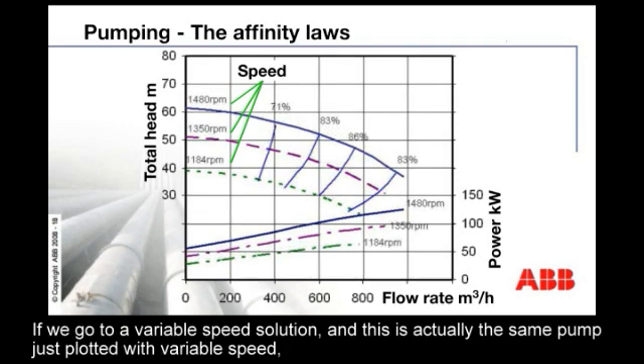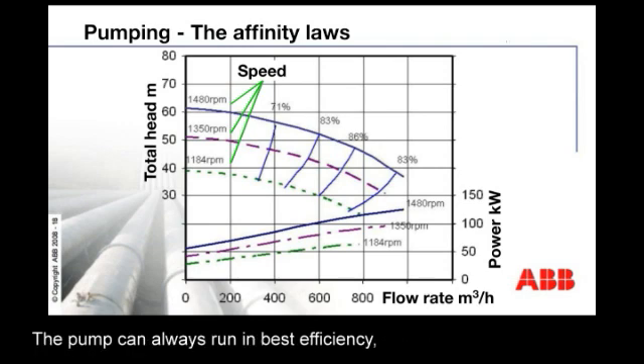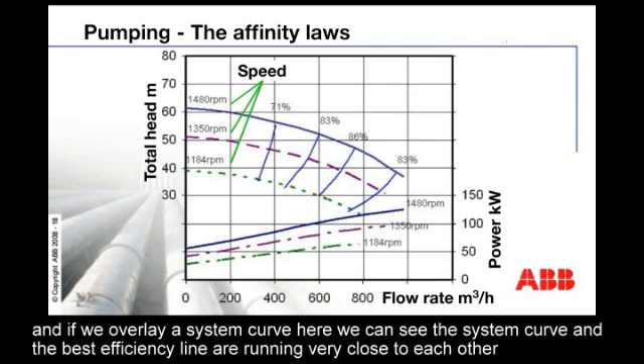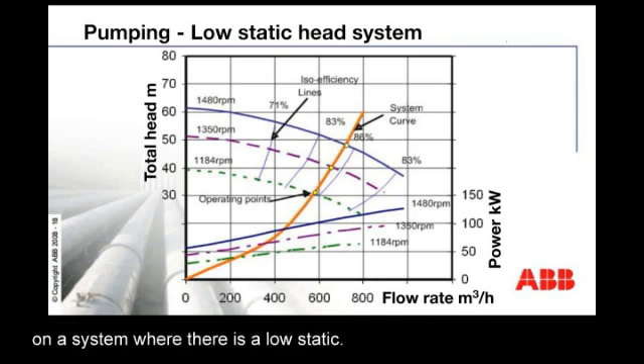If we go to a variable speed solution — this is actually the same pump, just plotted with variable speed — you can see that the efficiency curves have changed shape. The pump can always run at best efficiency. If we overlay a system curve, we can see the system curve and the best efficiency line running very close to each other on a system where there is a low static head.